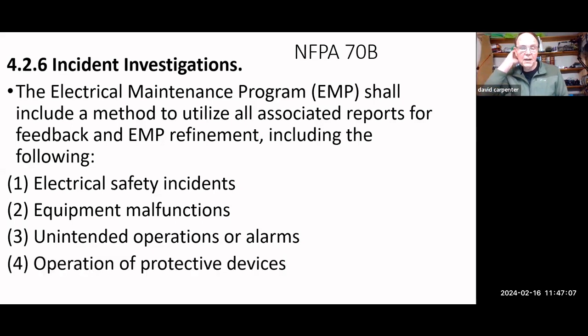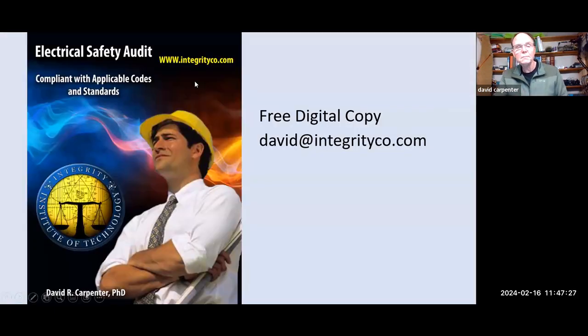Operation of protective devices. If you have a malfunction, for example, of a circuit breaker, it could be that the breaker's frozen. If it's frozen, that means inside they've had an arc in there at some point and it's actually welded the contacts together. This is a dangerous situation. You've got a breaker that's really not working, but it's allowing current to go through it.